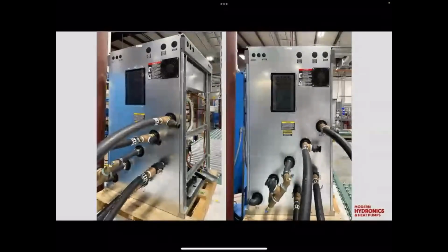You can see here, I mentioned the electrical knockouts across the top for the backside of the unit. And then this right here is the intake grill for the inverter cooling fan. And this dark colored piece that's over that is actually a magnetic air filter that's accessible from the backside of the unit, and it's a washable, screen style filter. So it's real easy to maintain and can just be removed and cleaned as needed.